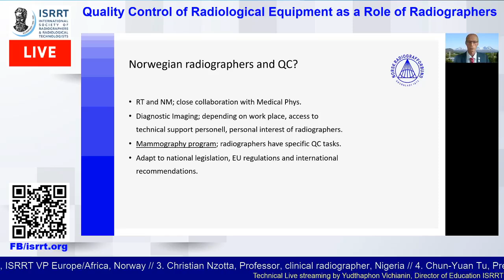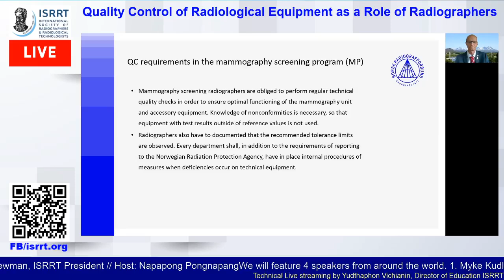Now, back to the mammography program. Mammography screening radiographers are obliged to perform regular technical quality checks in order to ensure optimal function of the mammography unit and accessory equipment. Knowledge of non-conformities is necessary so that equipment with test results outside of reference value is not used. Radiographers also have to document that the recommended tolerance limits are observed. And every department shall, in addition to the requirements of reporting to the National Radiation Protection Agency, have in place internal procedures of measures when deficiencies occur on technical equipment.